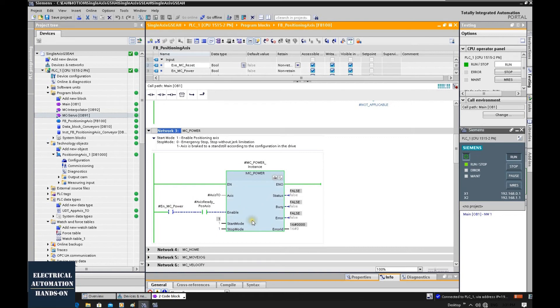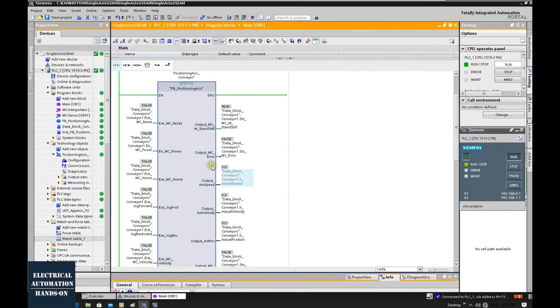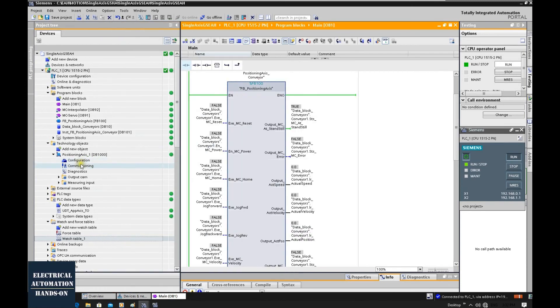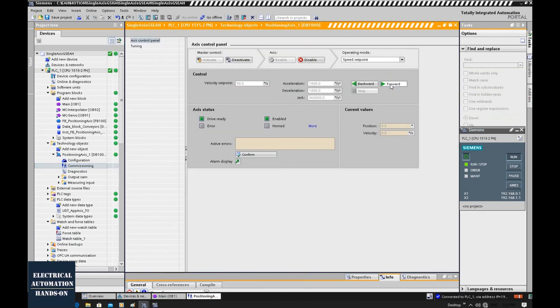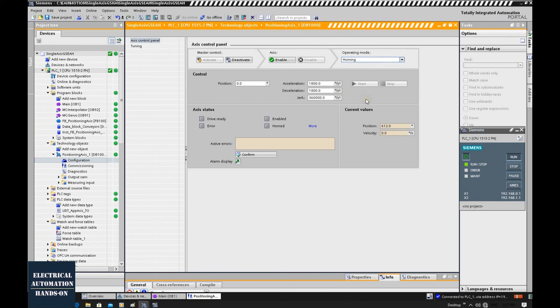Using this watch table we can watch and monitor the axis status, and use the variables to control the axis. In actual cases, before using a program to control the axis, it is highly recommended to use the commissioning control panel first. This lets you verify axis movement — for example, verifying forward/reverse direction and speed settings. If we set 200 millimeters per second, we need to verify this makes sense for our mechanical system.